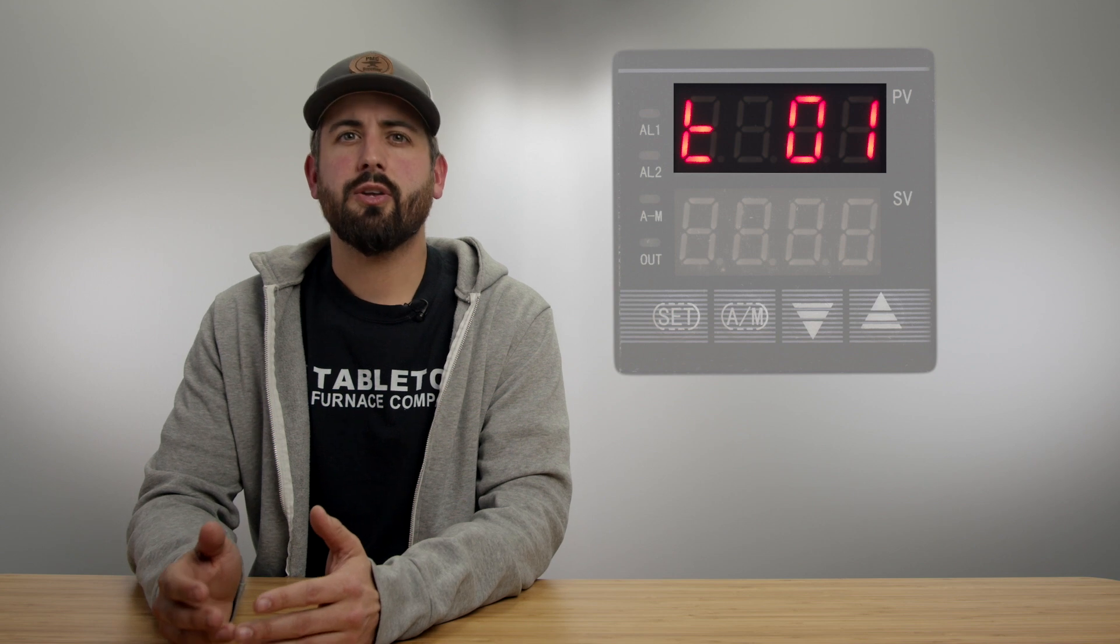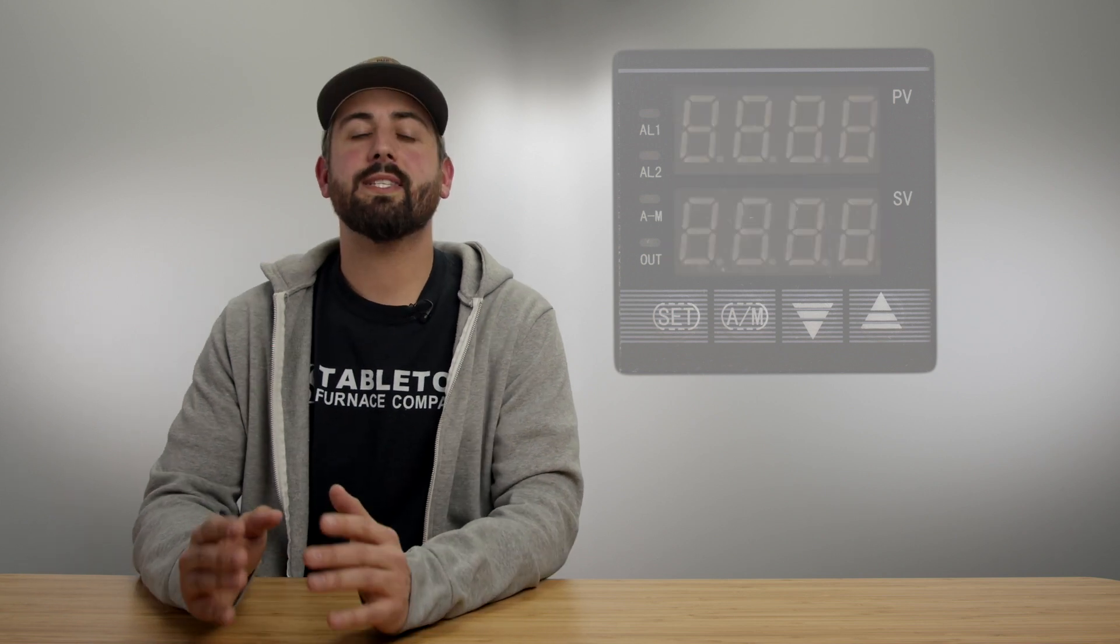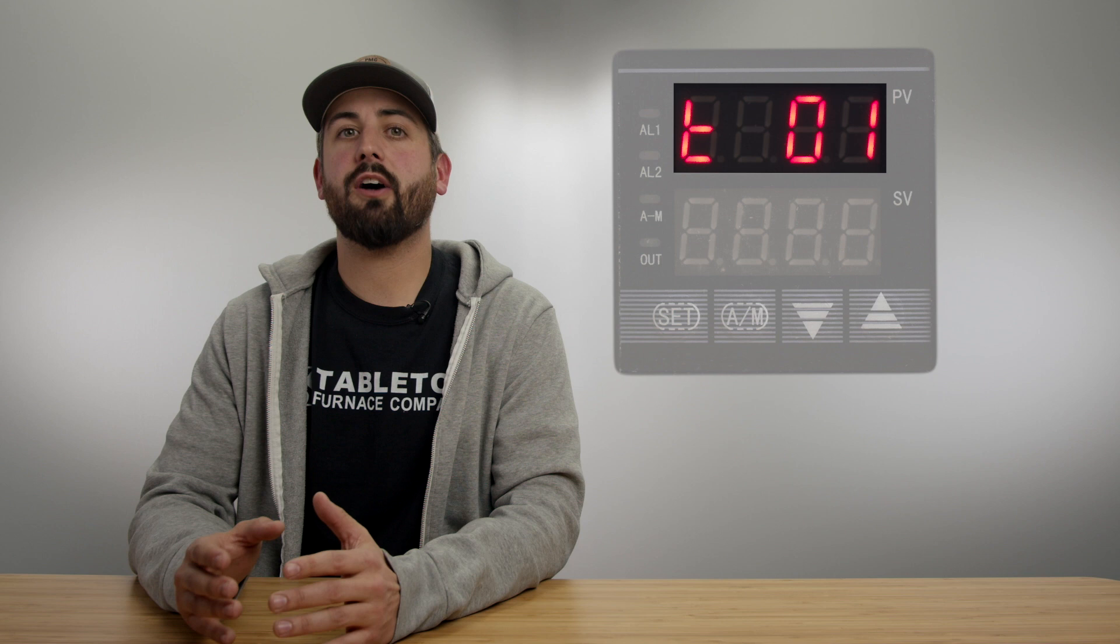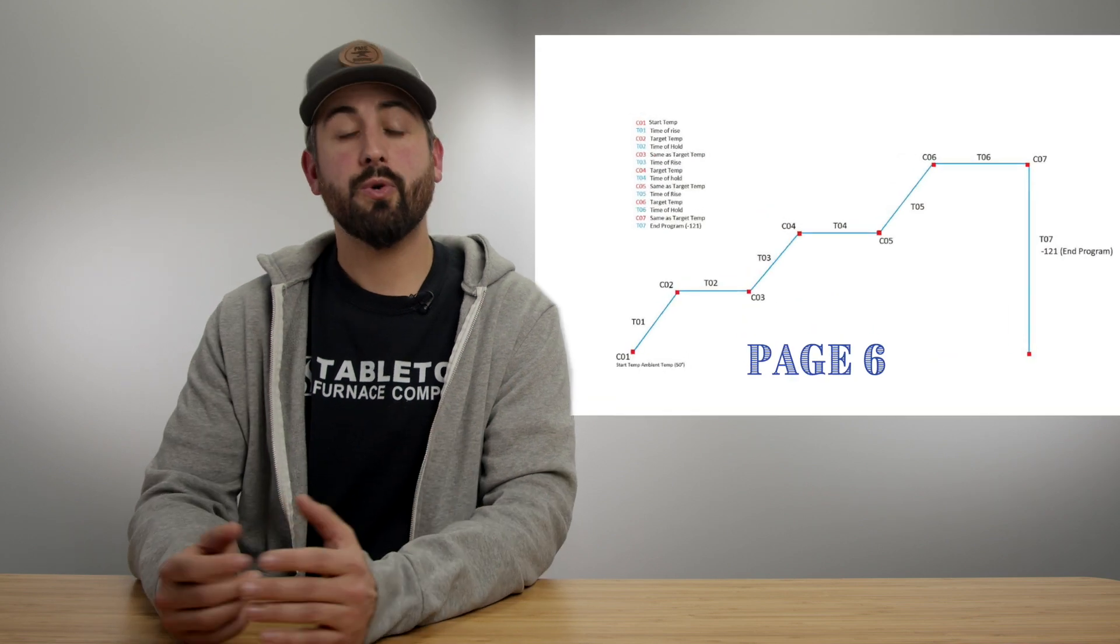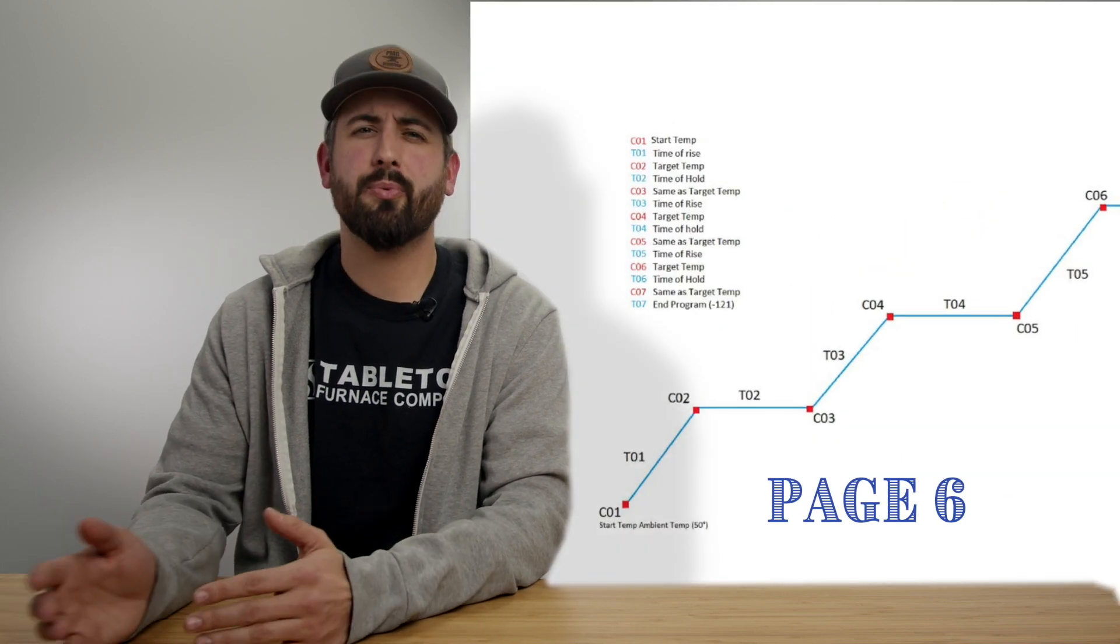We're going to show you how to set the initial burn-off program. These are going to be the same steps you use when you're setting your own programs in the future. Your program is going to consist of a series of C and T codes. Your C values are going to represent temperatures while your T values actually represent times. Remember C codes always represent a temperature and a T value is always going to represent a time.